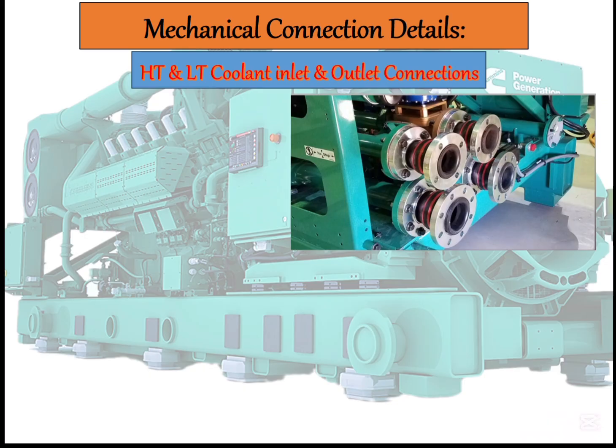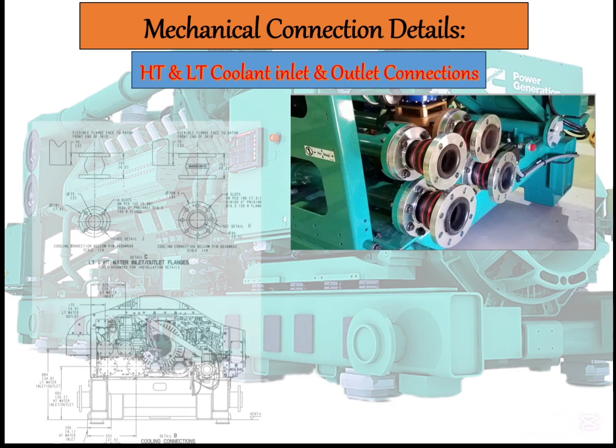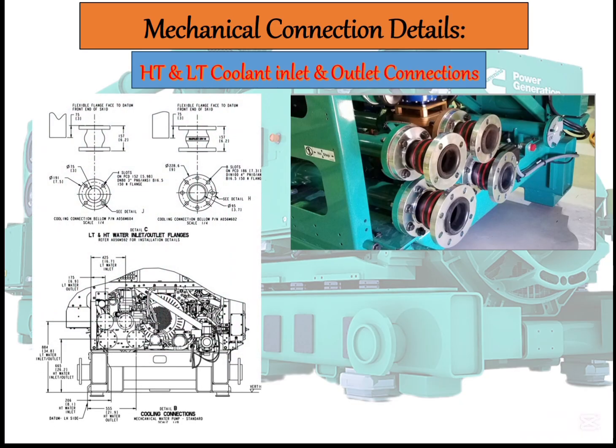If we look at the front side of the engine, below the air filter housing, we can see 4 pipes. In the last picture, we also mentioned LT in, LT out, HT in, HT out. The first thing we look at in those connections is that we use rubber flex joints to absorb the vibrations when the genset is in operation. The HT line is a 4-inch line and the LT line is a 3-inch line. That is DN100 and DN80 connection.